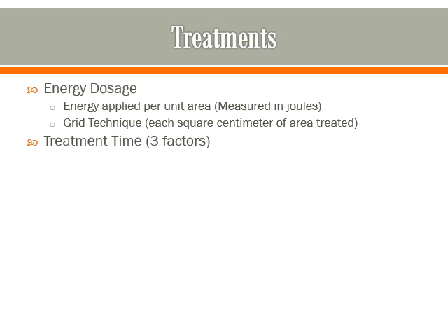It's going to be influenced by the average power output and the dosage you want to achieve. As we said, the power output of a laser is fixed. The only thing you can really alter is time. And the idea is you're looking at your dosage. Your dosage itself is based upon three things: the average output power, time of light exposure, and the treatment area. So see how all of these things interact when you're determining that. But that's what you want to look at.